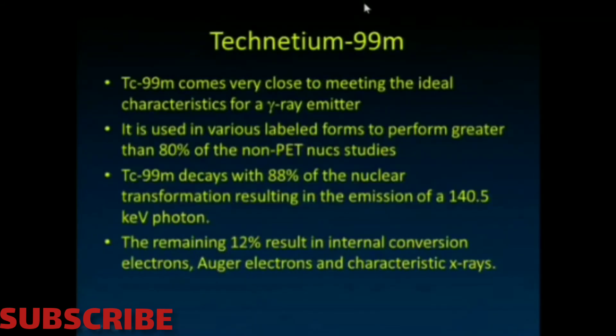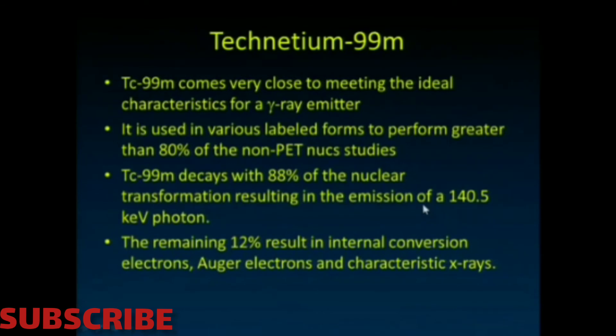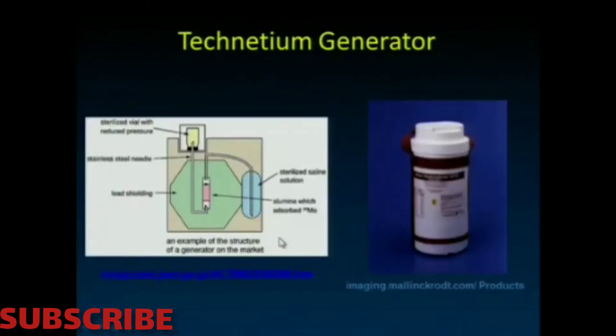Technetium-99m as a radionuclide comes really close to the ideal properties we talked about — that's why you see it used in various labeled forms to perform greater than 80% of non-PET nuclear studies. It decays with 88% of its nuclear transformations resulting in the emission of a 140 keV photon, which is ideal: it escapes the body, yet is still low enough that we can stop it fairly readily with our detector. Unfortunately the remaining 12% results in energetic electrons that deposit dose in the patient, but that's a relatively small amount. For this reason, a lot of chemistry has been developed around technetium.